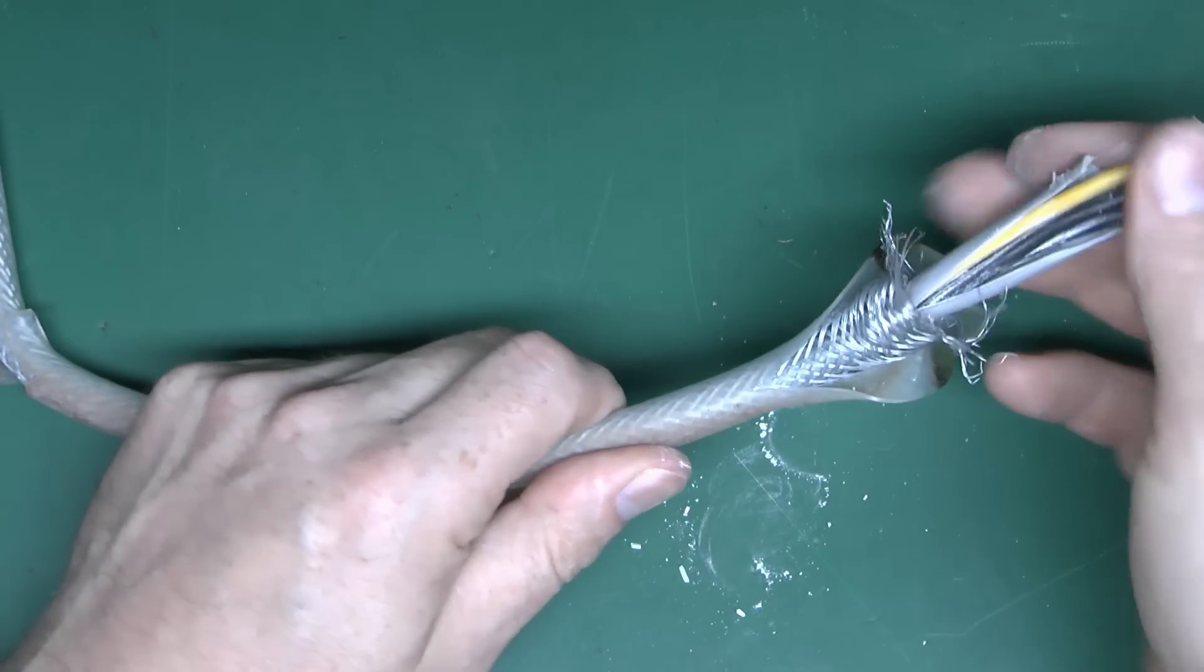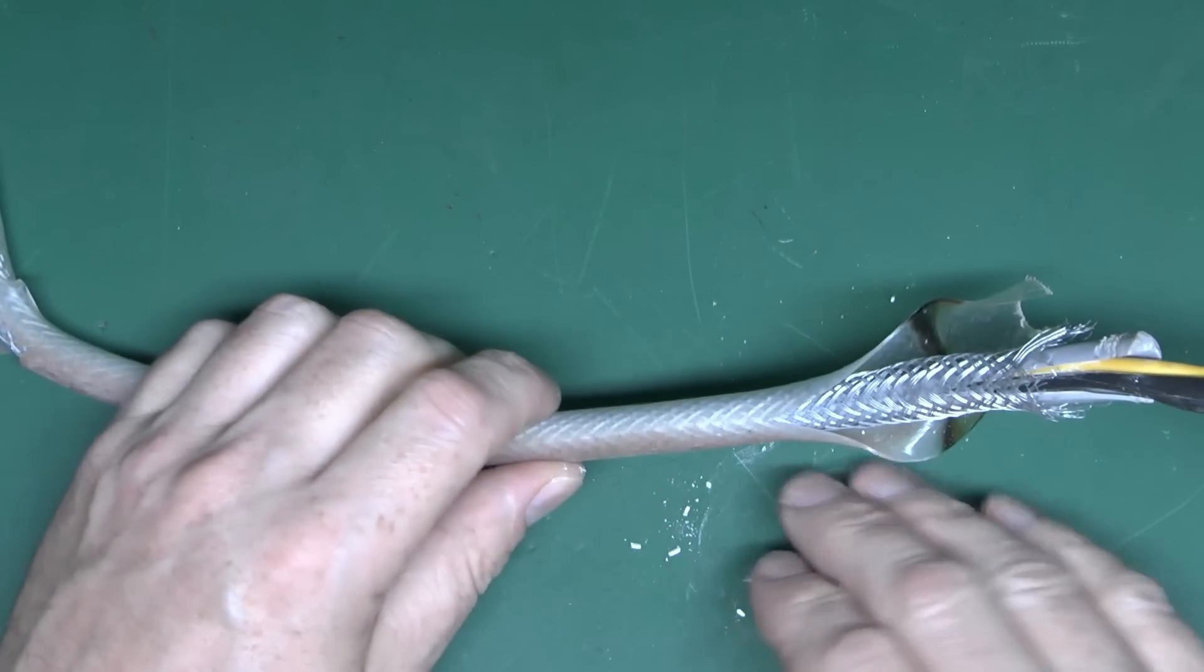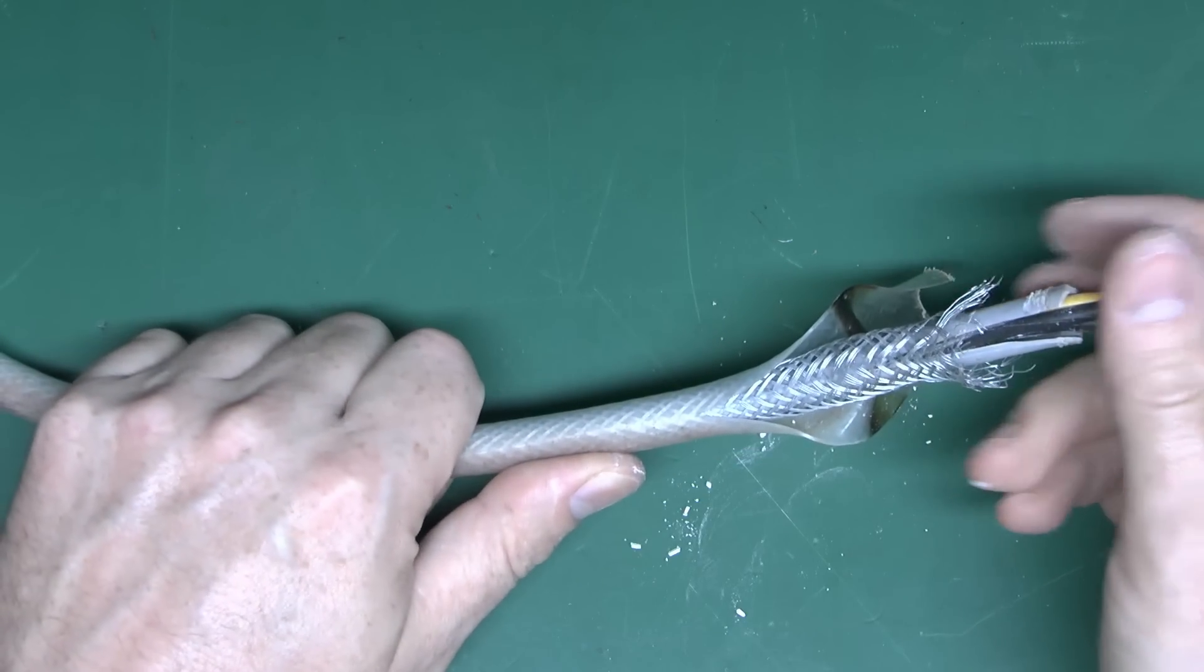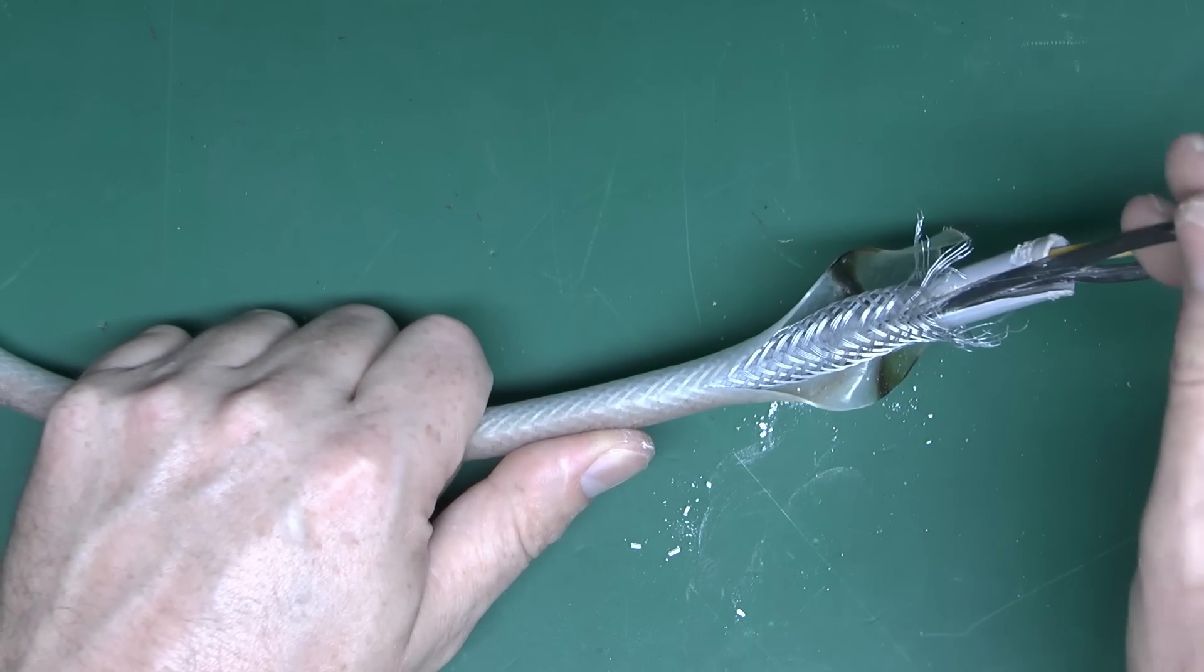Now the problem with this particular cable is a lot of people seem to believe that it's some kind of armoured cable, and you could use it outside, or bury it in the ground, in the same way you would do with armoured cable now. That's completely incorrect. This is not armoured cable.